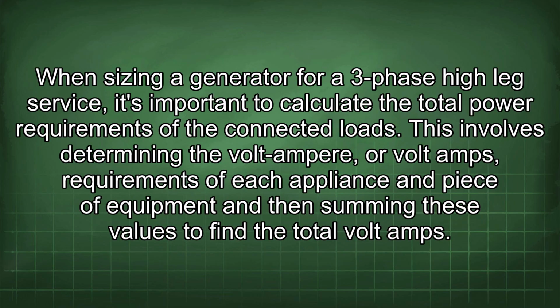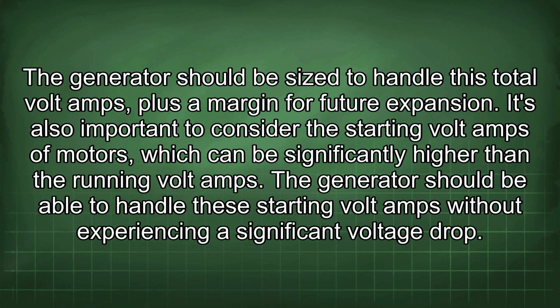to the grid. When sizing a generator for a three-phase high-leg service, it's important to calculate the total power requirements of the connected loads. This involves determining the volt-ampere, or volt-amps, requirements of each appliance and piece of equipment, and then summing these values to find the total volt-amps. The generator should be sized to handle this total volt-amps, plus a margin for future expansion. It's also important to consider the starting volt-amps of motors, which can be significantly higher than the running volt-amps. The generator should be able to handle these starting volt-amps without experiencing a significant voltage drop.